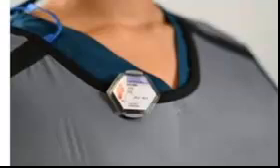noise becomes more pronounced as the dose is reduced. Because the FPD-TFT is often integrated into the radiographic unit, the variable speed option is readily available to customize the speed for each imaging protocol. Minimize patient dose by selecting projections and exposure factors with least patient dose.